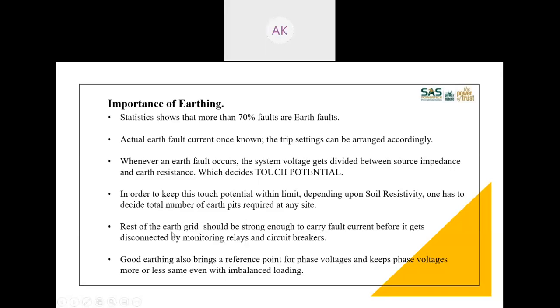Okay. The rest of the earth grid should be strong enough to carry fault current before it gets disconnected by monitoring relays and circuit breakers. Whenever an earth fault current flows, obviously, ultimately, a breaker has to operate to disconnect the source from that fault. Otherwise, the fault current will never stop until it gets cleared. Your entire earthing system should carry it without getting damaged.